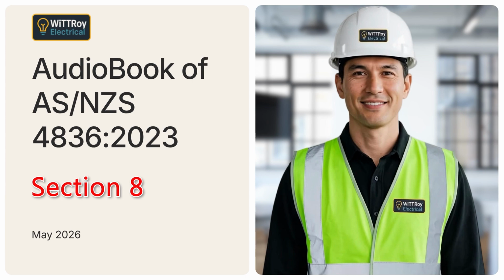An RCD does not protect against every electrical danger. An RCD may not protect if there is no current path to earth. It may not protect if the tool contacts another source of electricity, such as a drill bit hitting a hidden live conductor inside a wall, floor, or ceiling. It does not protect against electric shock or electrocution between the electrode and return leads when welding. It may not protect where the current leakage path is from active to neutral or from phase to phase. It also does not provide protection for a portable electric tool supplied from an isolating transformer or isolated winding generator.